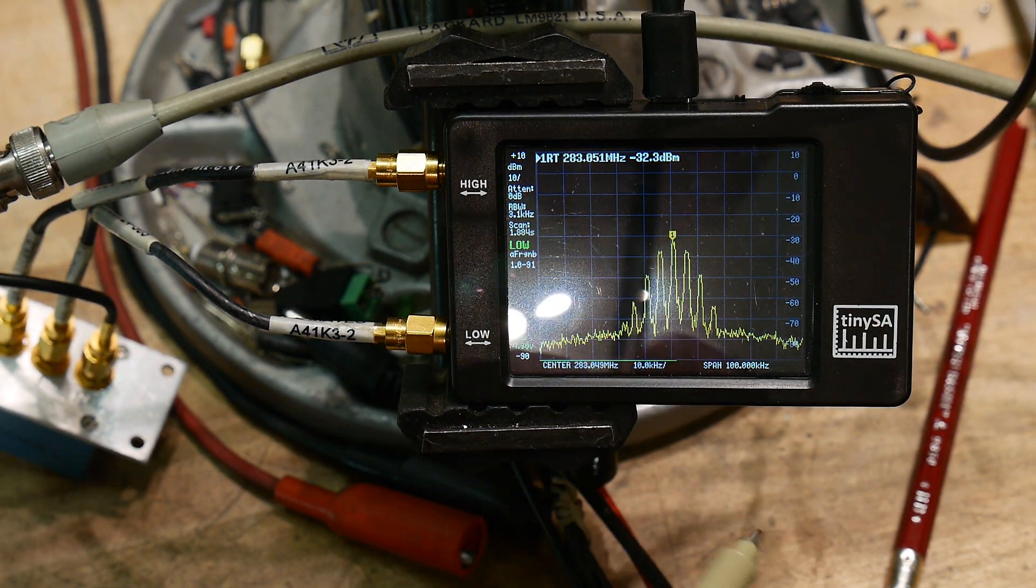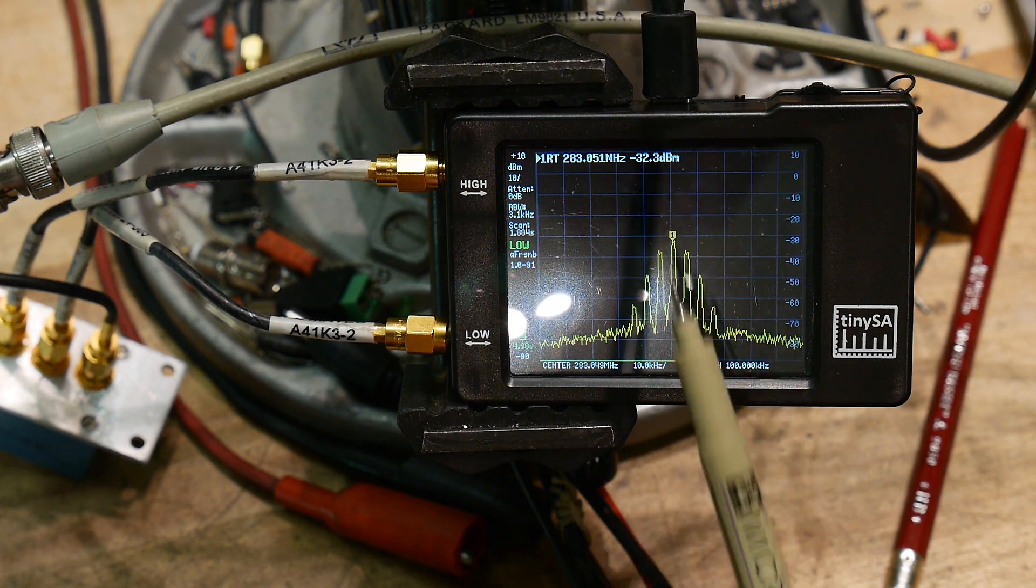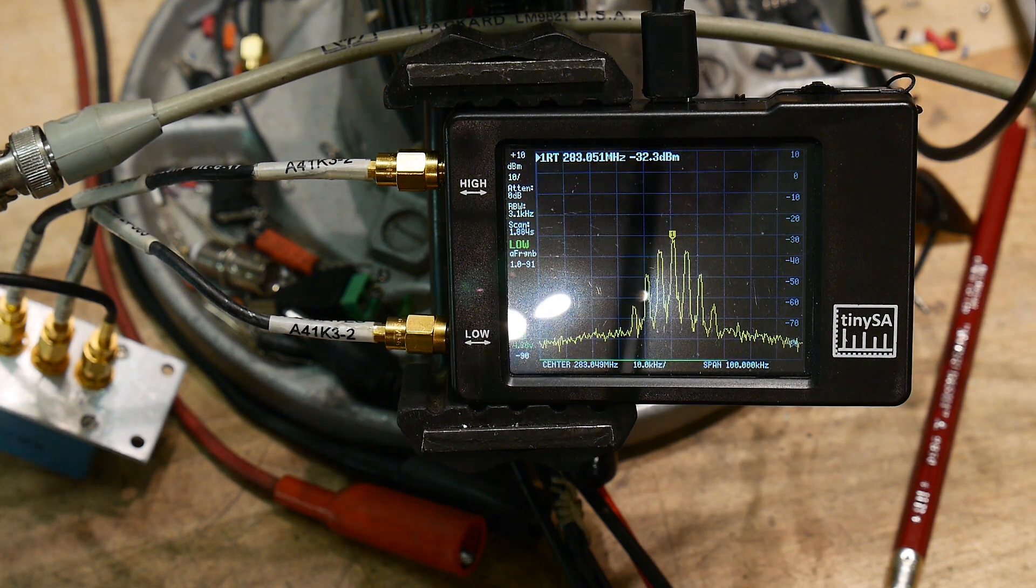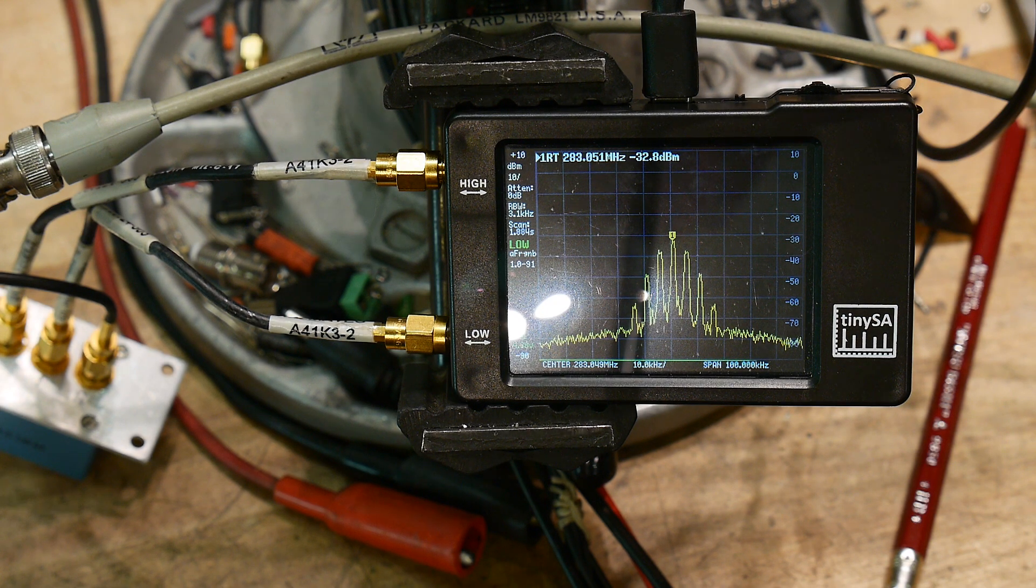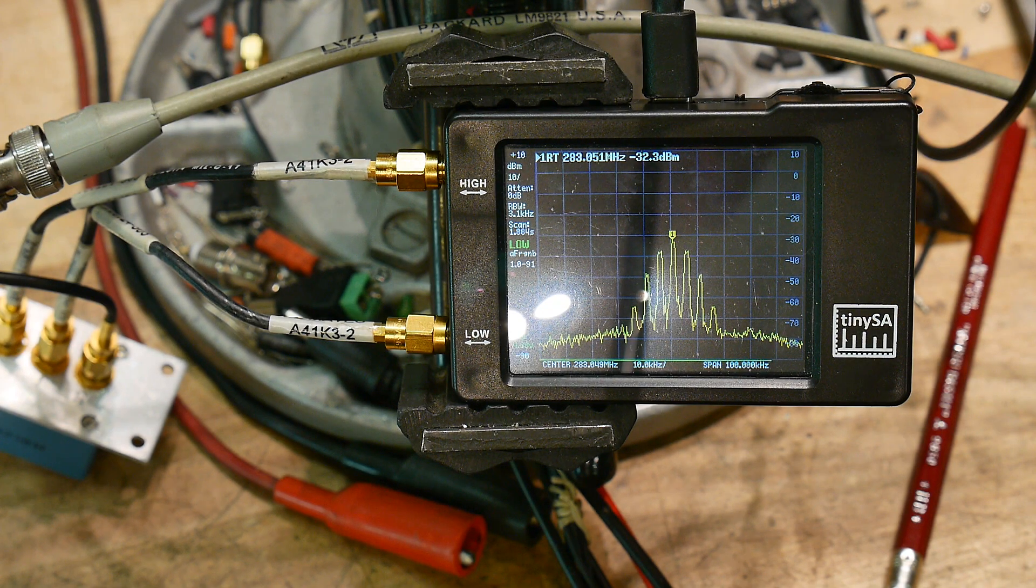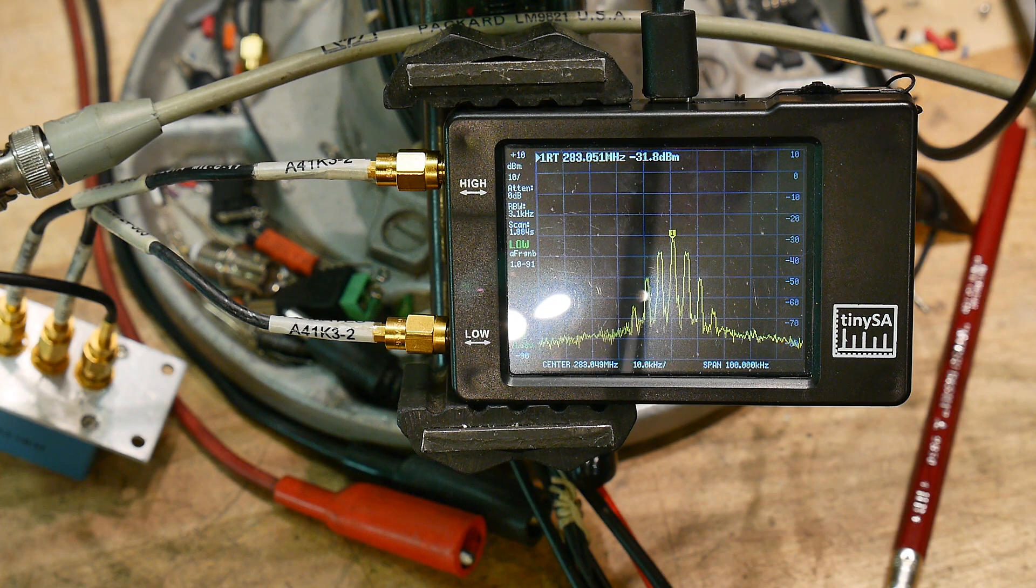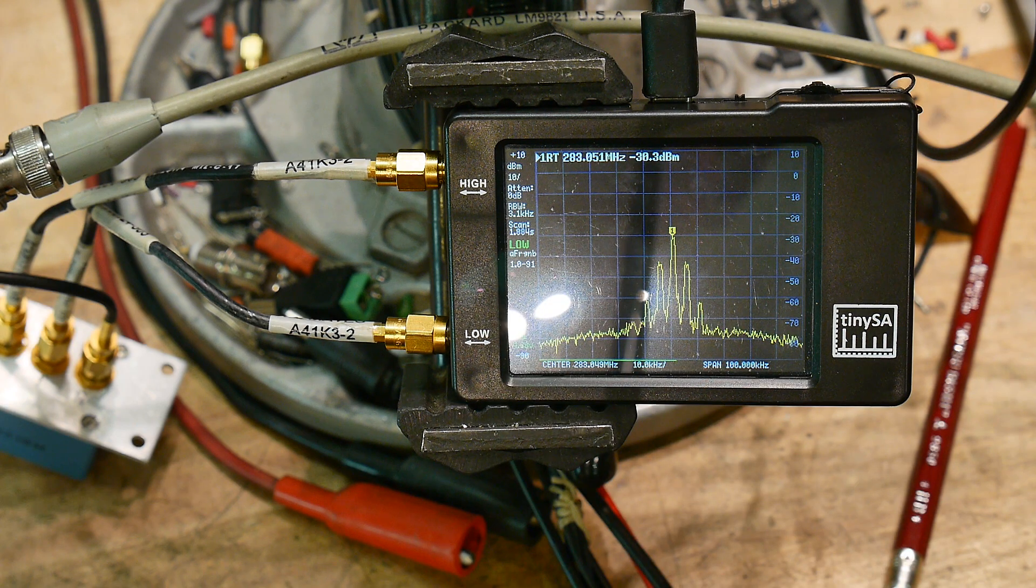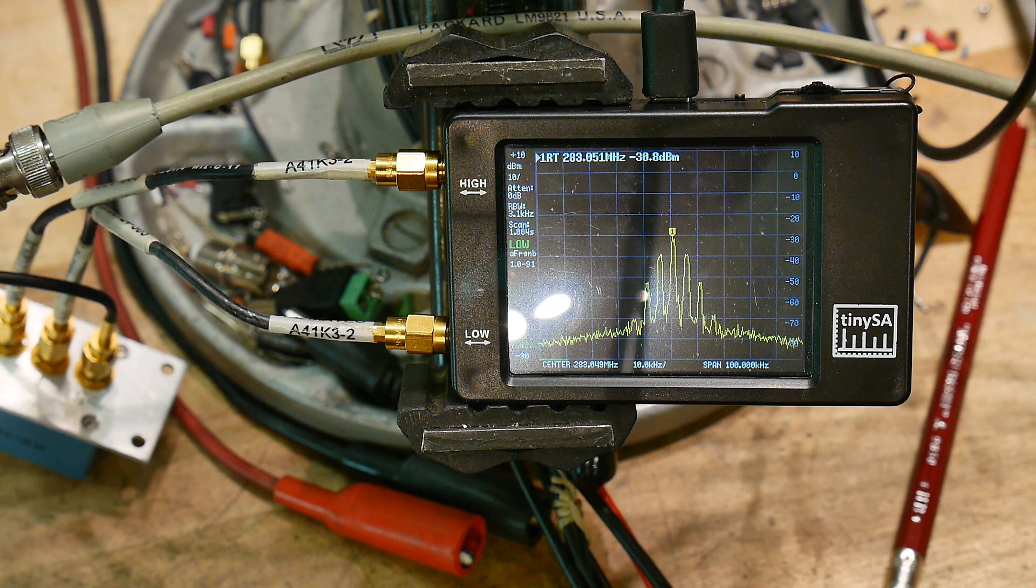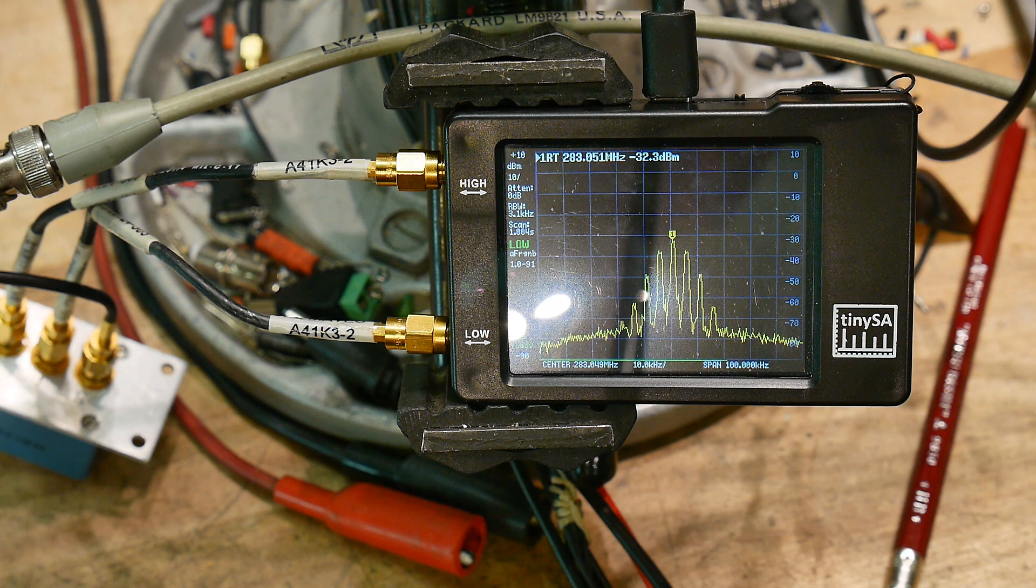Alright, so what we see here is a sweep of some signal, and it's an FM modulated signal, so it's very nice. I can change it here. I'll go over to the RF generator and I will change the deviation. I'll make the deviation smaller, and you can see it getting narrower. I'll put it back to 10 kilohertz, which is where it was.